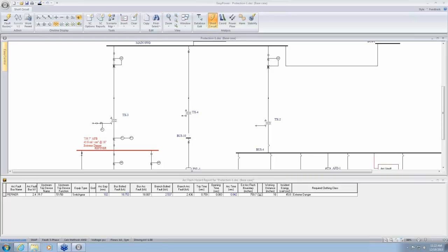So I guess one of the methods that we have recommended is lowering the time limit, that is the maximum time limit in the short circuit options. Some people have forced it to a low calories and that's fine too. Right now we do not have a whole lot of test data on how much incident energy you might get on small lighting circuits because there's not a whole lot of test information or any calculation procedures that have been prescribed yet. So I would say just go to our website, download that paper on 250 volts and less. Next question.